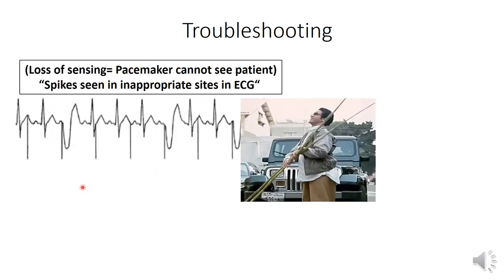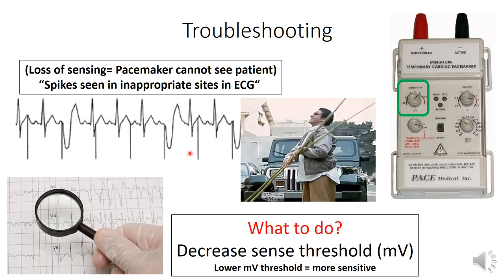The other problem is loss of sensing — the pacemaker cannot detect the patient's heart rhythm and fires regardless, which we diagnose by seeing pacemaker spikes at inappropriate times, such as on the T wave. The solution is to decrease the sensitivity threshold so that with a lower millivolt threshold the pacemaker becomes more sensitive, can detect the native heart rhythm, and inhibits itself appropriately.